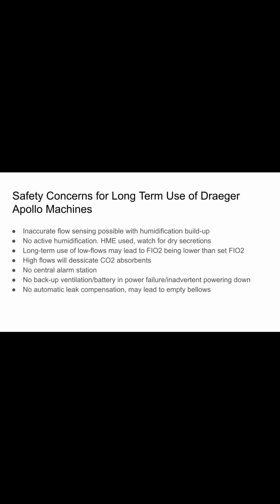We also need to be mindful that we do not have a central alarm station for these ventilators, so one anesthesia provider at minimum needs to be present in the PACU at all times while we are running these ventilators. In case of alarms, someone who is familiar with these machines has to be present to be able to troubleshoot it and make sure the patient's okay. Also be mindful that we do not have a backup in the event of electric failure on these ventilators. So even if you inadvertently hit the power switch, the patient will not be ventilated at all. So really be mindful and watching these patients closely, and we will have, as you saw, an ambu bag ready at every station in case of any issues like this.